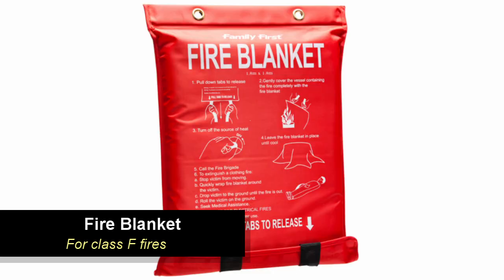Fire blankets should be located in the vicinity of the fire hazard they are to be used on, but in a position that can be safely accessed in the event of a fire. They are classified as either light duty or heavy duty. Light duty fire blankets are suitable for dealing with small fires in containers of cooking oils or fats and fires involving clothing. Heavy-duty fire blankets are for industrial use where there is a need for the blankets to resist penetration by molten materials.